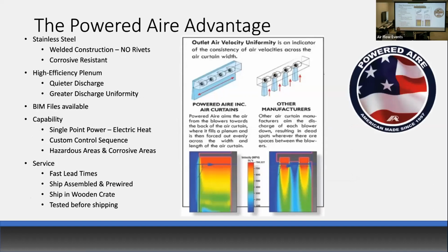Just quickly talking a little bit about powered air. As I mentioned, noise is one of the biggest complaints we get when talking about air curtains. People imagine these loud jet engines that blow people's hair all around. What most manufacturers do is they take their blowers and they point them directly out of the nozzle. So imagine you have a 4-inch blower shooting air out of a 2-inch nozzle. It's creating a lot of turbulence, also dead spots, and a lot of noise.